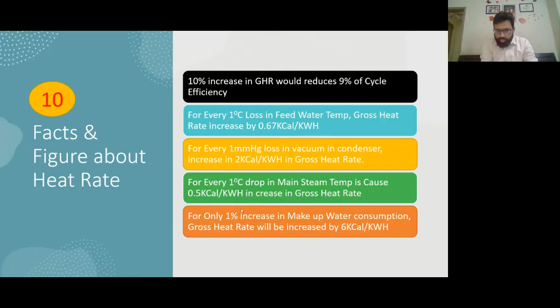Similarly, for main steam temperature, if there is a 1 degree drop, then 0.5. For makeup water, if our makeup water is increased, then it impacts the heat rate by 6 kilocalorie. A 10% increase in auxiliary power consumption increases the net heat rate by 1%. Similarly, if the absolute pressure at the TG inlet drops by 1 bar, then the heat rate increases by 1 kilocalorie per kilowatt hour.